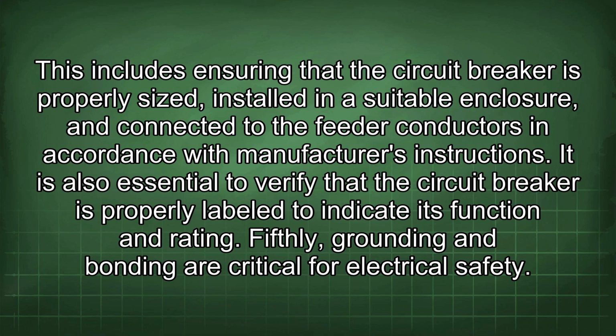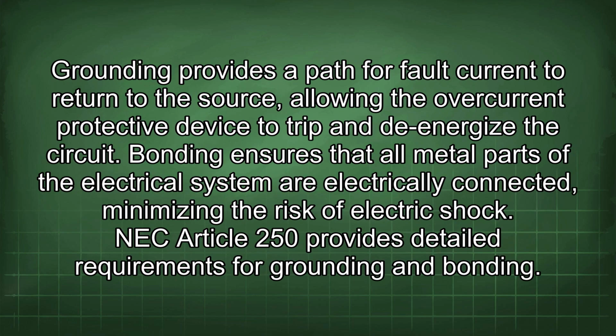Fifthly, grounding and bonding are critical for electrical safety. Grounding provides a path for fault current to return to the source, allowing the overcurrent protective device to trip and de-energize the circuit. Bonding ensures that all metal parts of the electrical system are electrically connected, minimizing the risk of electric shock. NEC Article 250 provides detailed requirements for grounding and bonding.